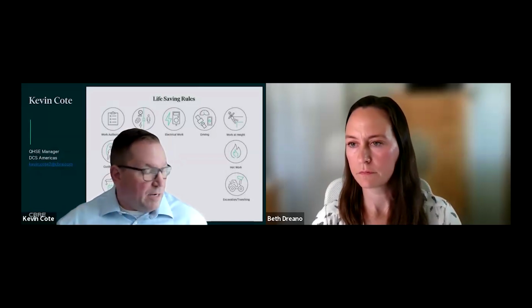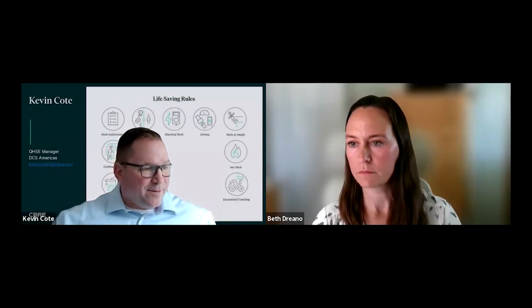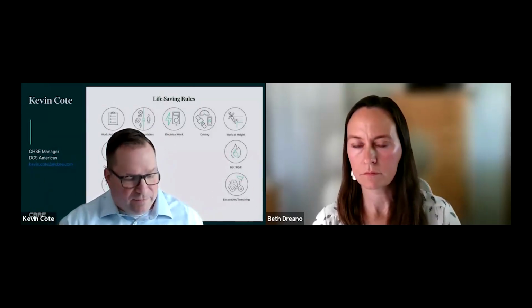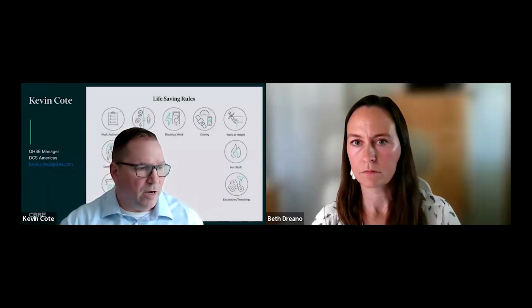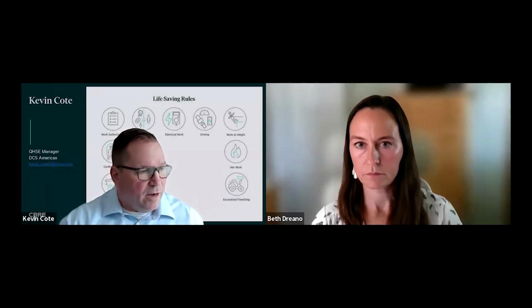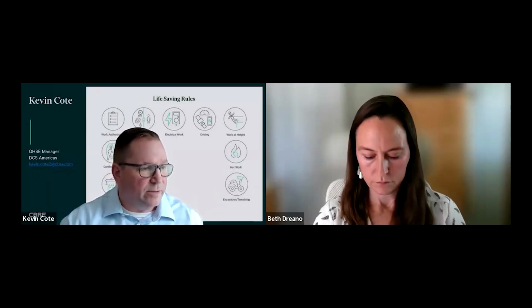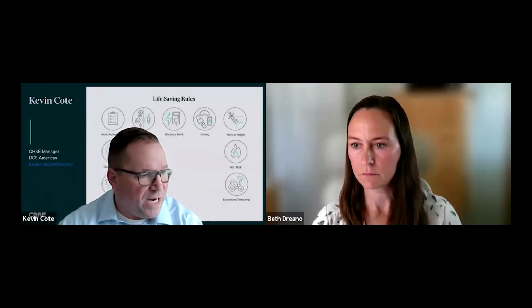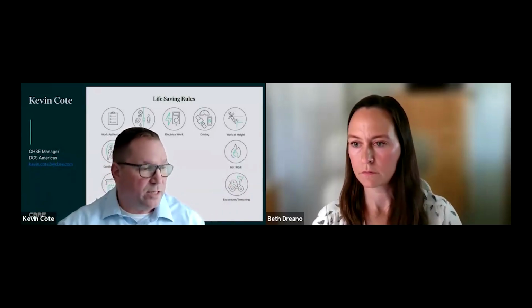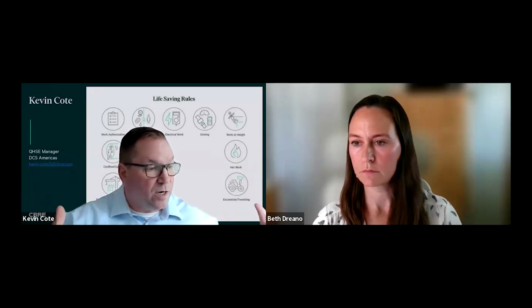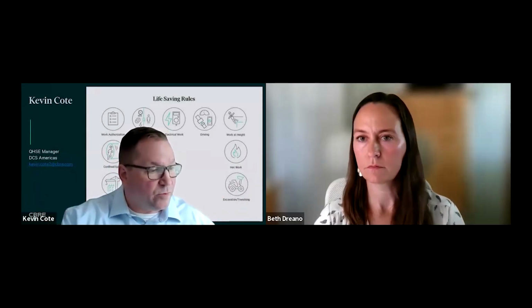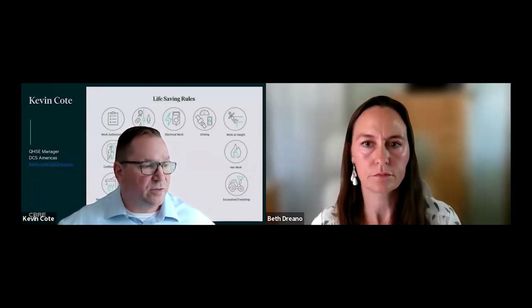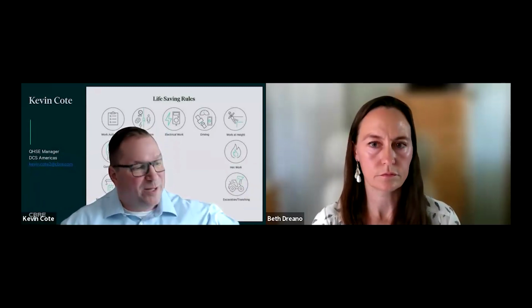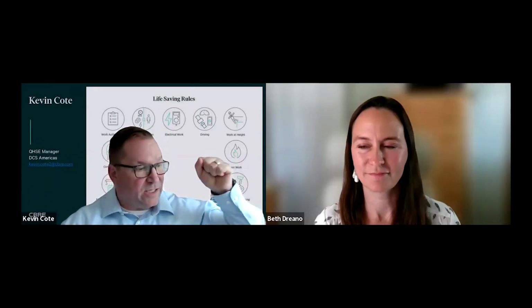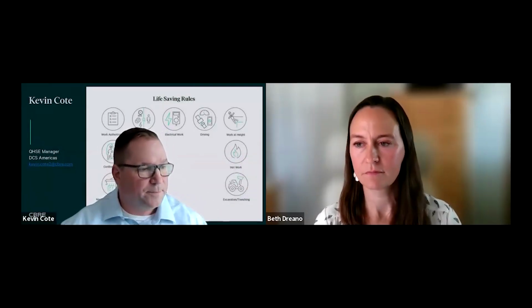Overall the data center is grounded. We follow NFPA, off the top of my head I think it's 780 or 785, for grounding systems and also lightning. That system is inspected annually, or if things have changed inside the building, like if you did roof work and removed lightning rods and put them back up, you would recertify your system, to make sure that if the building is struck by lightning it has a place to go besides into your data center.